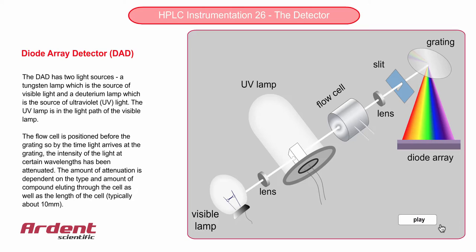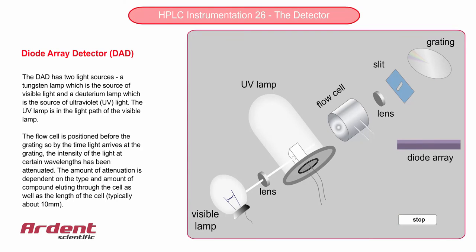This detector is capable of displaying 3D chromatograms, which consists of the usual time and response axes, but with the addition of a third axis, which is wavelength. This extra wavelength information can help confirm the identity of an unknown, and also can aid in peak purity.